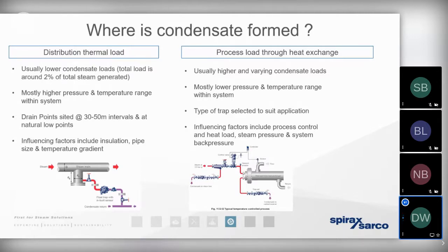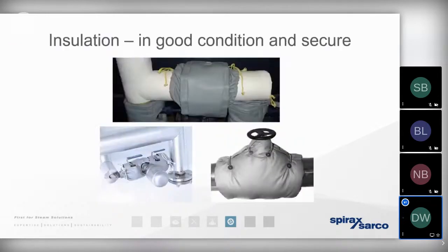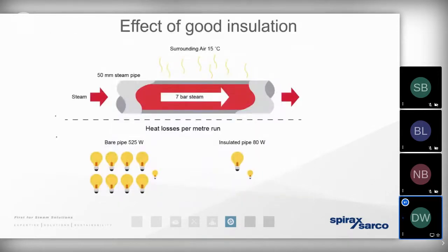So one thing that can have a significant impact on the amount of condensate that's produced in the distribution pipework is insulation. We've mentioned we always distribute steam in steel pipework at high pressure. And especially if we've got wet steam or oversized pipework, we expect that we can get a significant amount of heat loss. So we always use insulation, first and foremost, to protect against any health and safety incidents, but also to keep that heat loss to an absolute minimum.